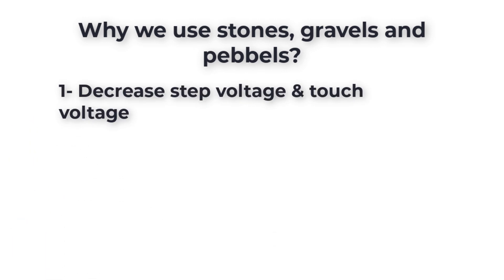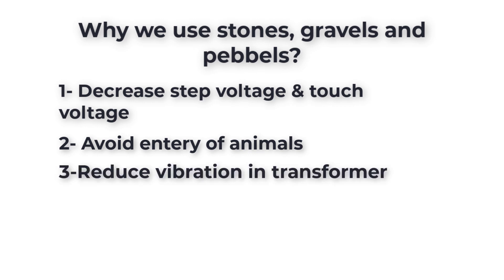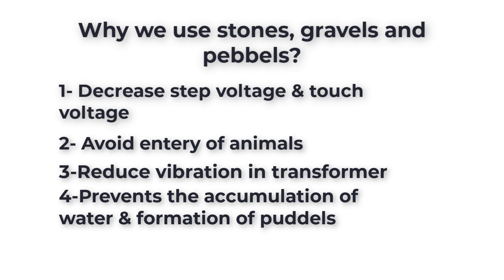Another reason for using stones beneath power transformers is to avoid entry of animals like rats, snakes, and lizards. For mechanical purposes, we use stones and pebbles to reduce vibration in the transformer. Stones and gravels also prevent the accumulation of water and the formation of puddles. Stones also eliminate the growth of small plants or grass, which can cause high moisture.